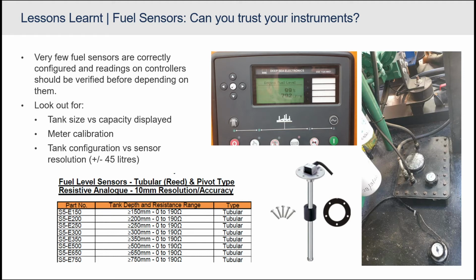I haven't encountered one instance where I came to a generator and we actually had accurate information, and there's various reasons for that. The first is that as soon as a generator gets installed, certain fuel sensors get installed with it that don't understand the scenario or configuration of that installation. The default settings on the controller are quite often overlooked and not set up for your specific installation, and that's normally the reason why it's not accurate. As soon as you pick that up, resolve the issue, and calibrate your sensor properly, then you can definitely trust your instruments.